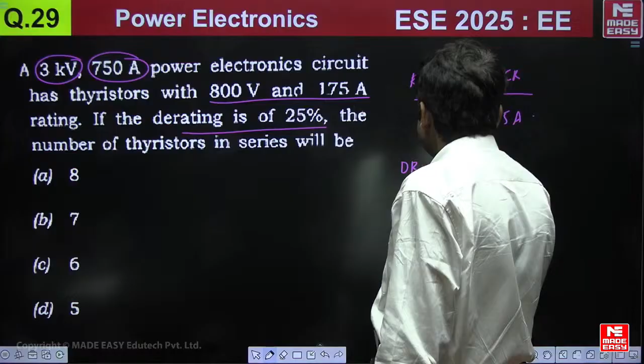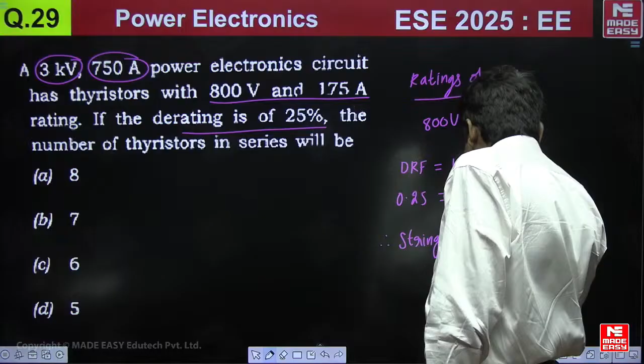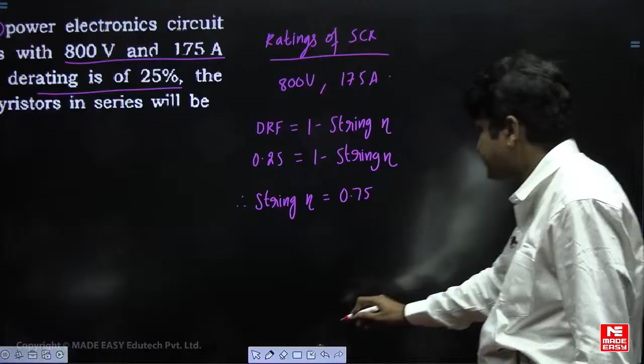The derating factor equals 1 minus string efficiency. Since it is 25%, 0.25 equals 1 minus string efficiency, therefore string efficiency is 75%, that is 0.75. The mathematical expression to calculate string efficiency is: string efficiency equals total string voltage divided by (number of series connected thyristors into individual voltage rating of each SCR).